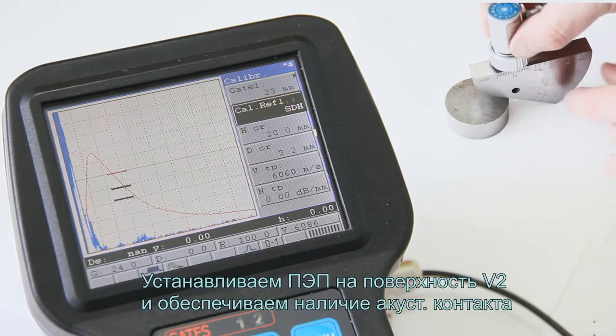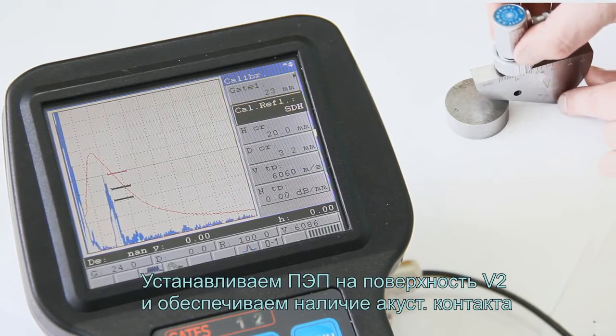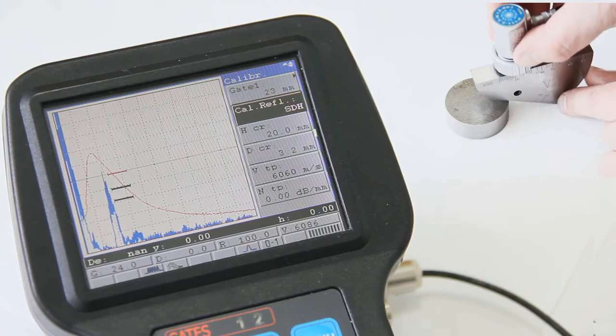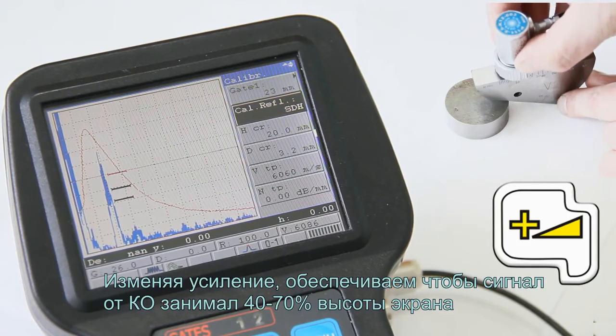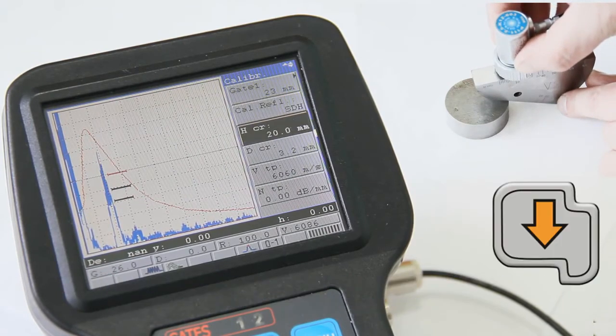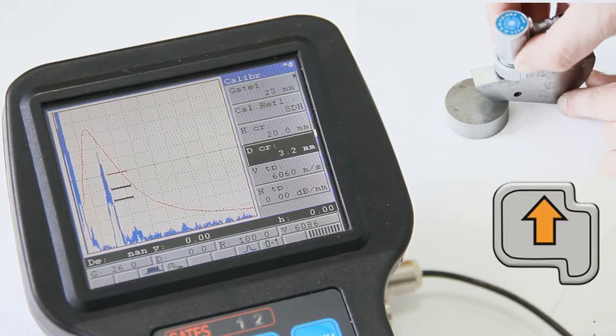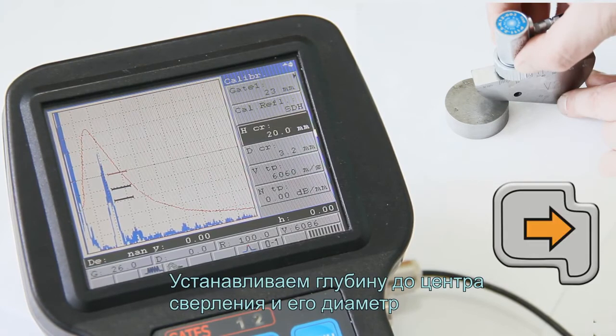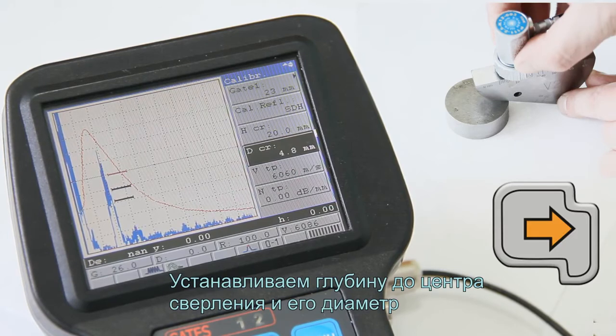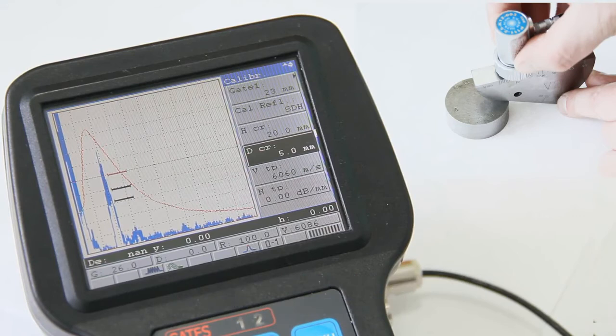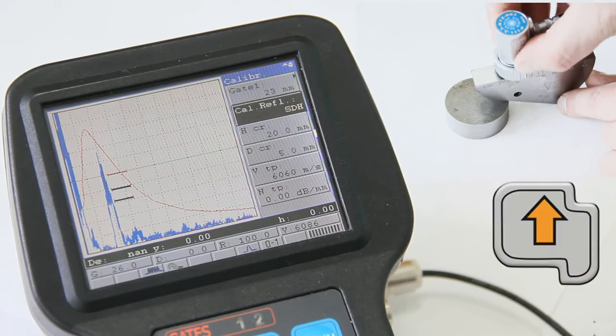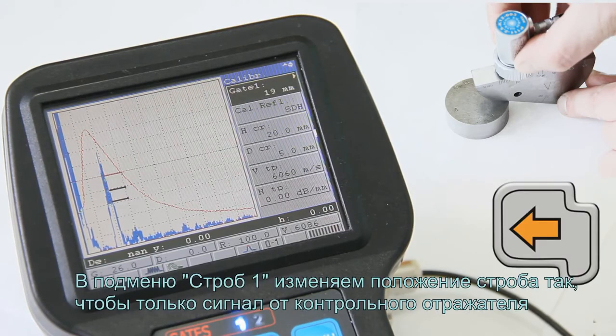Place the probe at V2 block surface and ensure the presence of acoustic coupling. By changing the gain, ensure the signal from the calibration reflector to be within 40–70% of the screen vertical scale. Set up the depth to the side drilled hole center and its diameter. In Gate 1 submenu, change the gate position in such a way that the signal from the calibration reflector to be within the gate and exceeded its surge level.